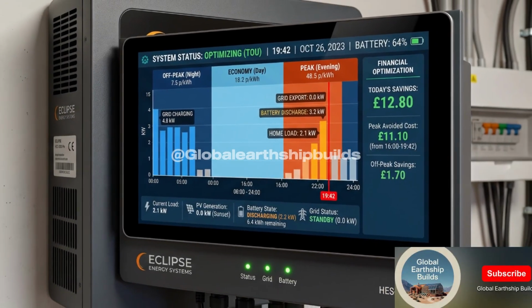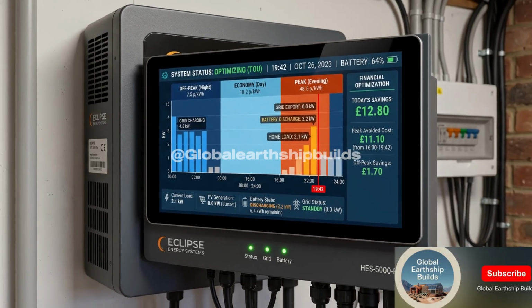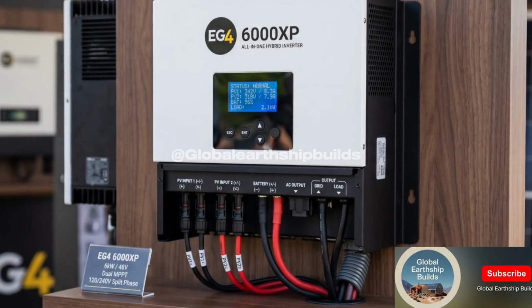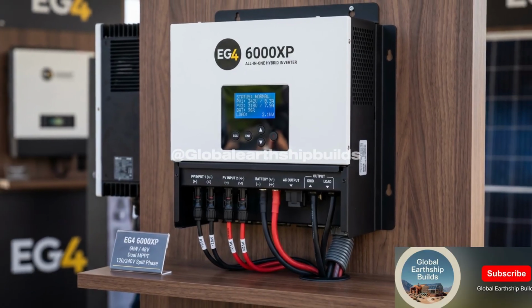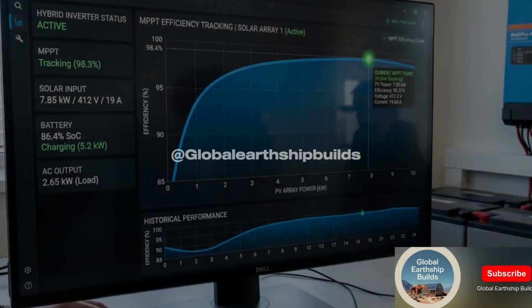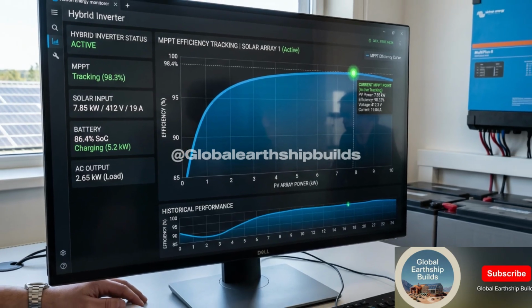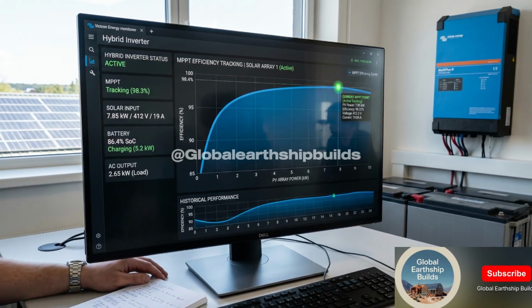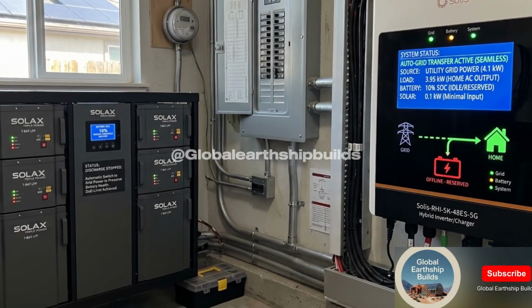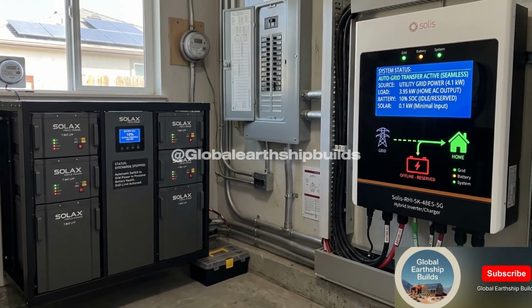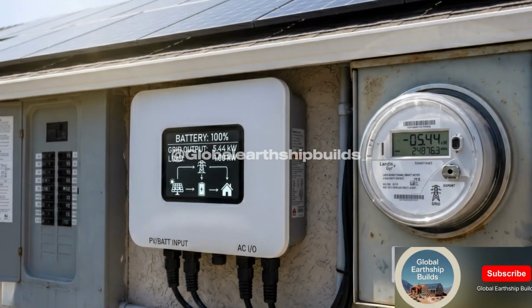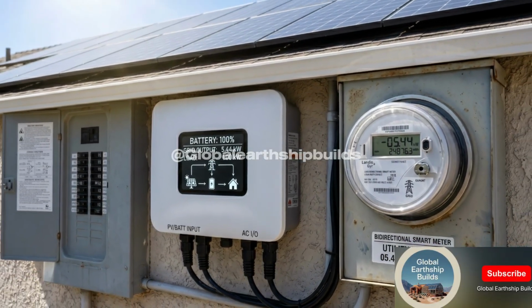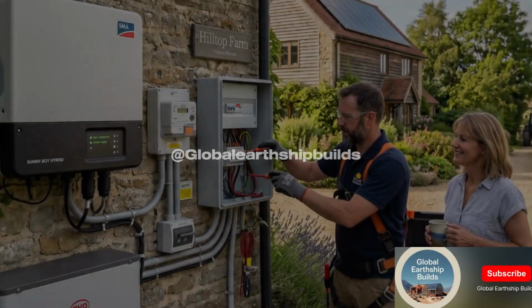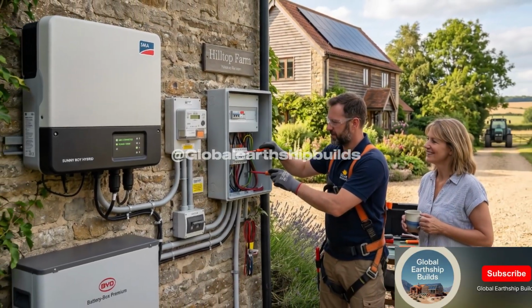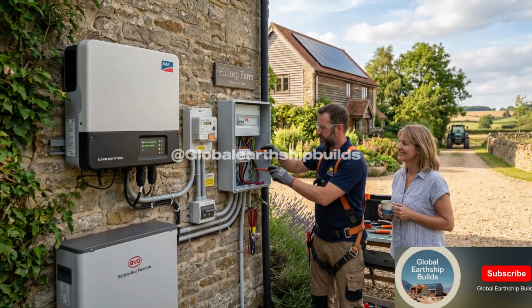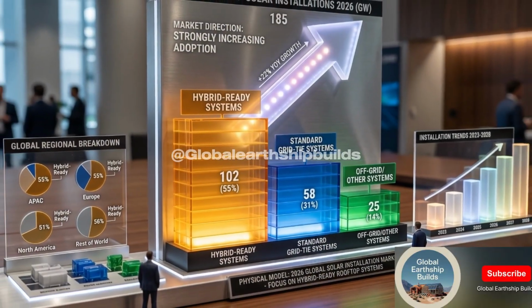That last capability, the ability to island and provide backup power during an outage, is something a standard grid tie inverter cannot do. A basic grid tie inverter shuts down the moment the grid goes down by law, because you cannot feed power back into downed utility lines with workers on them. A hybrid inverter has a transfer switch built in that disconnects from the grid first, then runs your home on stored power. The best units on the market in 2026 make that transfer in under 20 milliseconds, which is fast enough that most of your sensitive electronics never notice the interruption.